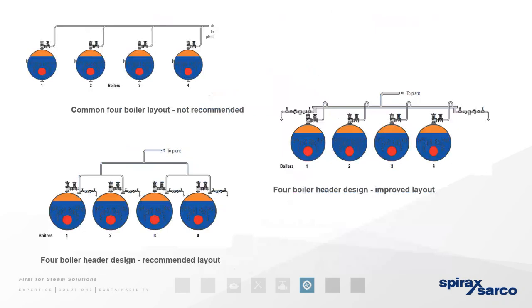Again, we're talking here about common four boiler layouts, which are not recommended, because effectively you can pressurize the other boilers. This is far more effective, where you're breaking them into twos, right, with headers. In the four boiler improved layout, we're going into one header coming into the top, allowing for even compensation, even load from each boiler.